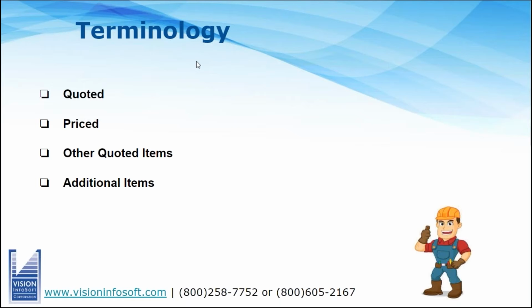Now, when you take off a switchboard or a panel, you have the option to put additional or other quoted items into that panel board or switchboard, things like circuit breakers and fusible switches, etc. And again, the program will assume that you're just going to get a quote on those, and it will plug in some labor for them. And then in all these modules, you also have the option to include additional items, things that you want the program to price. Maybe it's some Unistrut, maybe it's some additional accessories, things that you want the program to price, but not include in what you send out for a quote. So we'll cover that kind of subtlety here. That's kind of important as you go through the takeoff here.